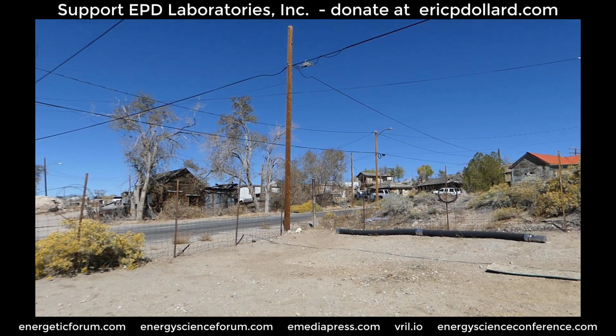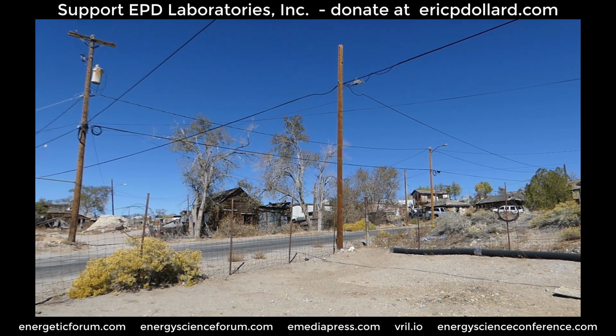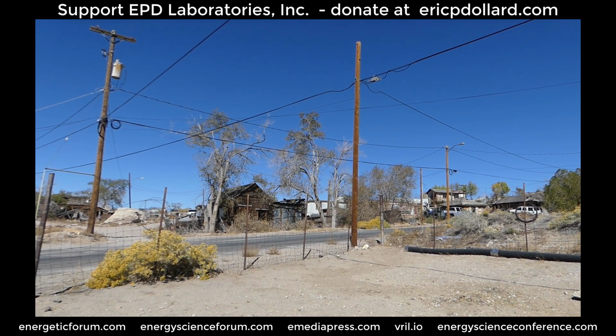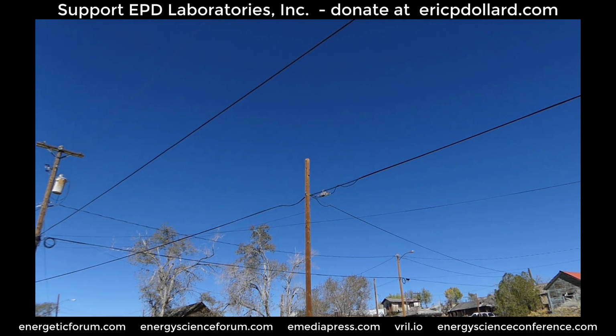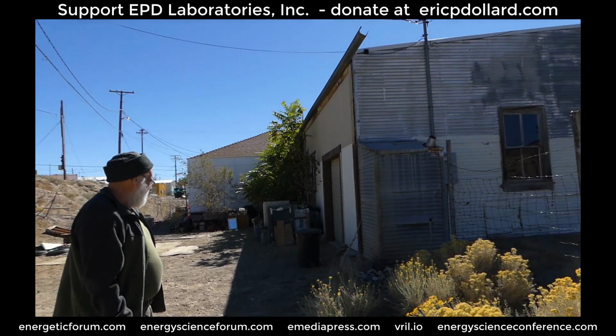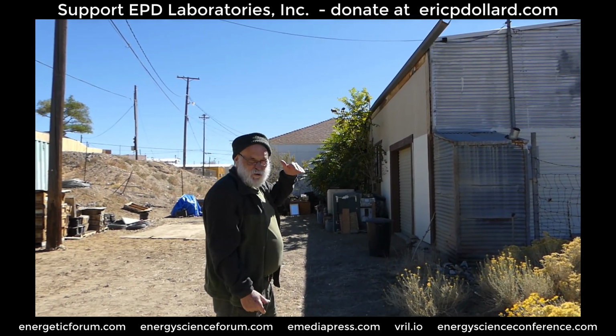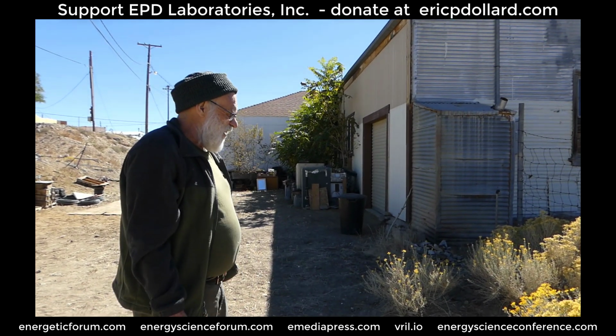So what will go in here is a symmetrical three-phase 480 volt Y-connected system. We won't use the neutral, and that will come into the building. And at that point, we wouldn't need an insulating pole because we'd be isolated, and then get metered for 440 rather than 220, and then the taps would be changed on the isolation transformers from 220 to 440, and that way we would have a completely symmetrical, relatively harmonic free, no neutral complication electrical system, which is the proper way to go about it.